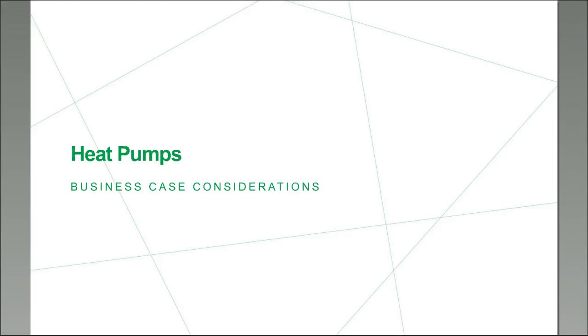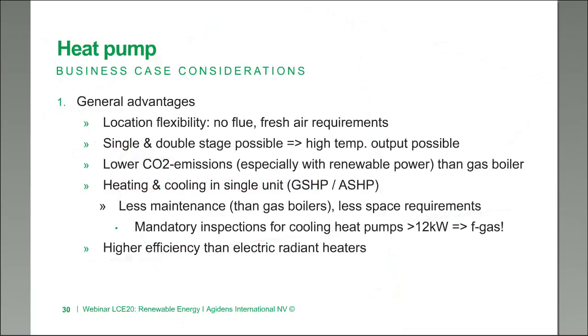When you think about what a heat pump can mean for your installations, it's important to have the right considerations. First let's look at the general advantages of using heat pumps. One advantage is the flexibility in where you locate the system. As opposed to a combustion engine — which usually needs fresh air supply and a flue for exhaust gases — that means you cannot just put a combustion engine in the middle or basement of a building. With heat pumps, this tends to be less of a limiting factor since you don't need a flue and don't have specific fresh air requirements.